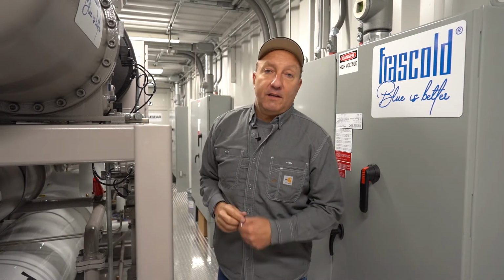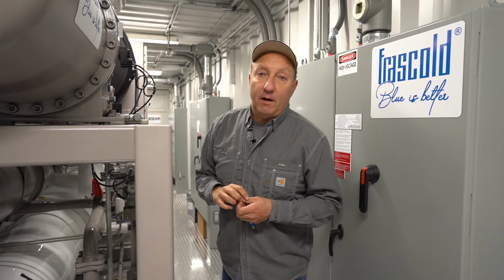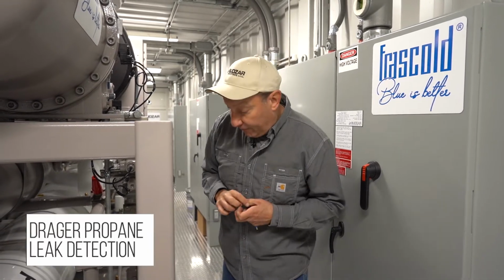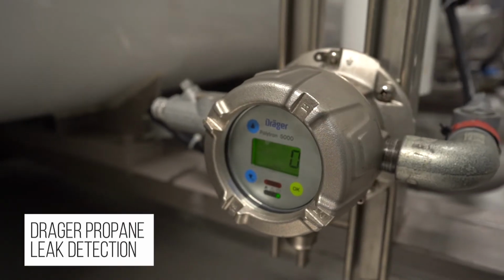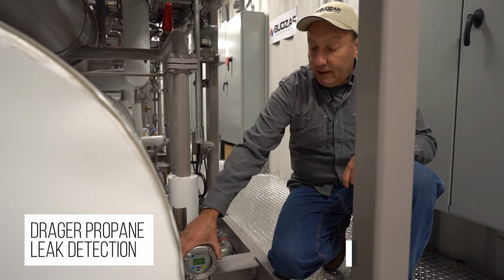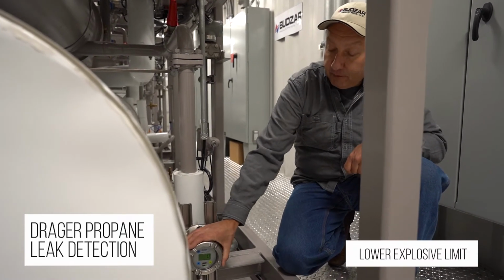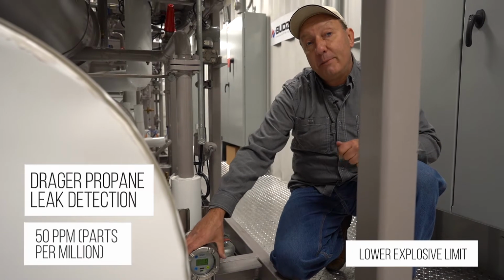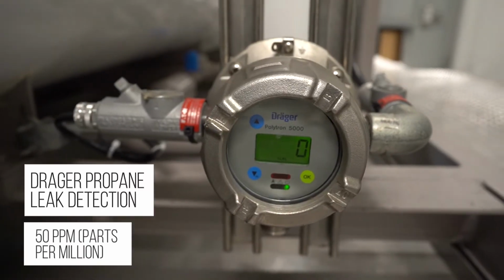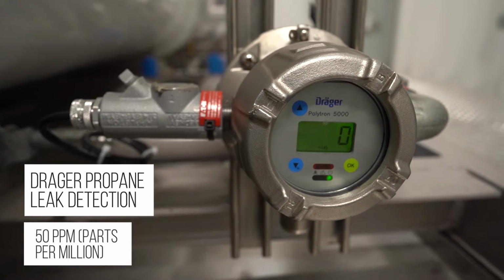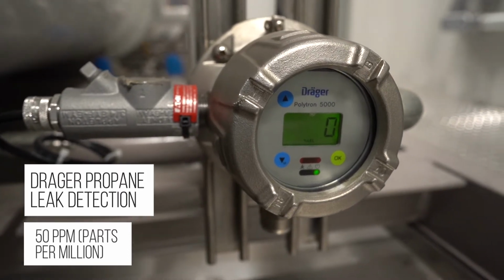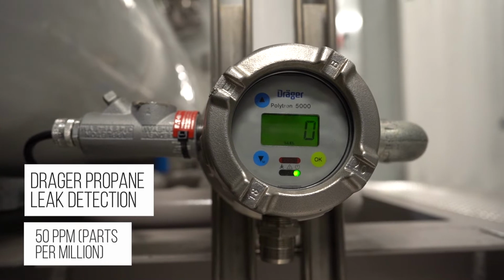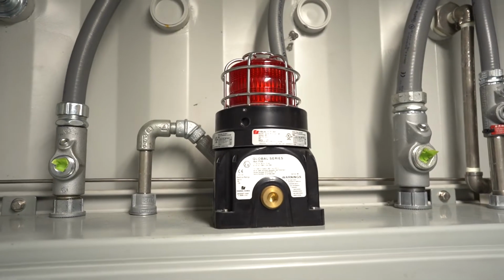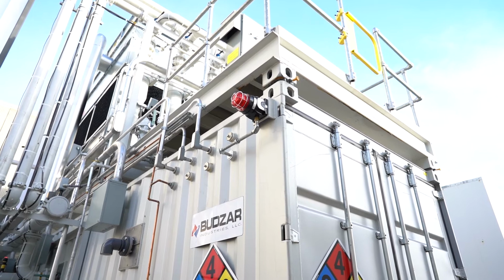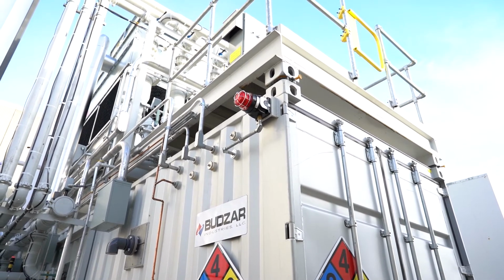Okay, now we're going to talk about the propane leak detection system. In this application, we're using a Dräger device. This is located right here. It is located low because the propane is heavier than air. This is an LEL, lower explosive limit sensor. We have it programmed for 50 ppm. If the propane in the container reaches 50 parts per million or higher, it's displayed here on the digital display, and this is what triggers the alarm. The audible and visual alarms throughout the container and outside of the container. This is a very important instrument for this system.